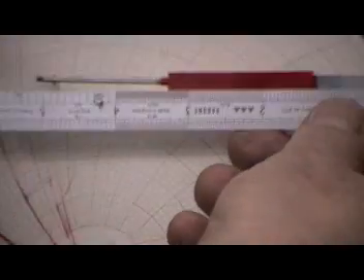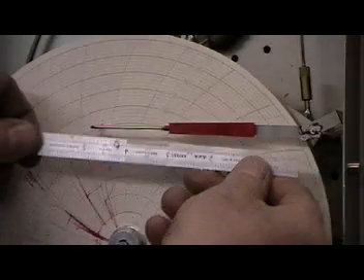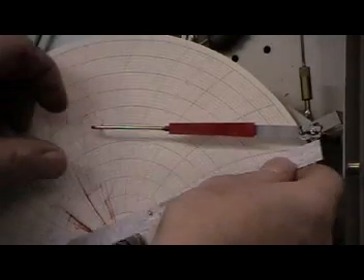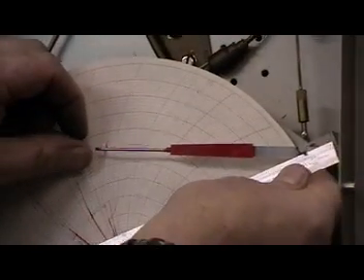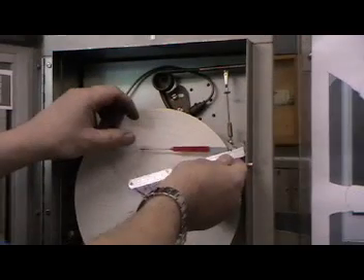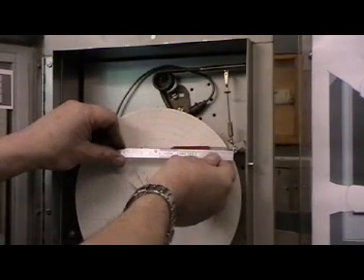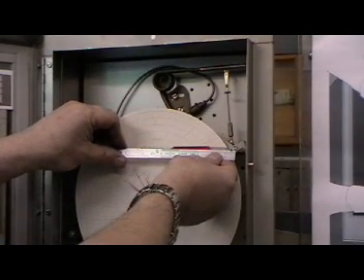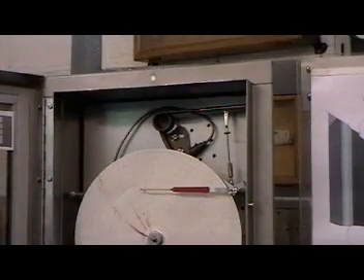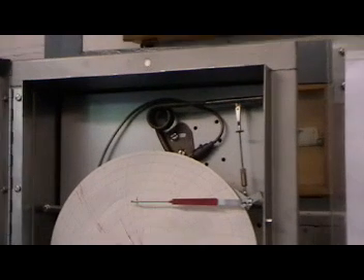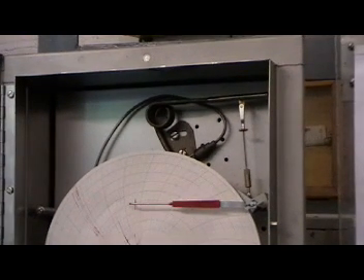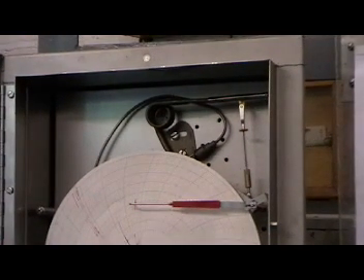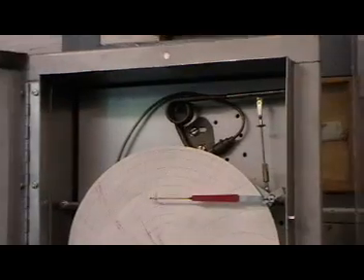Delinearization is from these two adjusting screws here. They've been left slack for speed of the video. And if you look at the parallelogram, the parallelogram doesn't apply. Because the pen is tilted up deliberately. And that's giving us more movement in the first half of the chart by raising the pen than the second half of the chart.